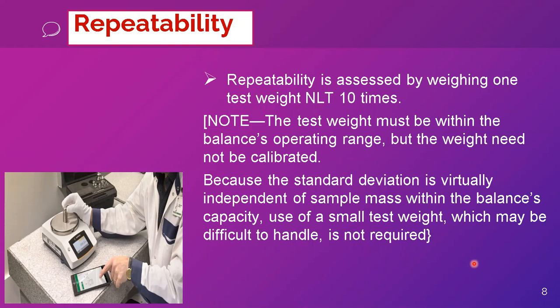The weight taken must be within the operating range of the balance. Whether it is calibrated or not is a separate matter. Because the standard deviation is virtually independent of sample mass within the balance capacity, use of a very small test weight that may be difficult to handle is not required. USP clearly states that you should not take such a small weight that is difficult to handle — just take one that you can handle and that is within the operating range.